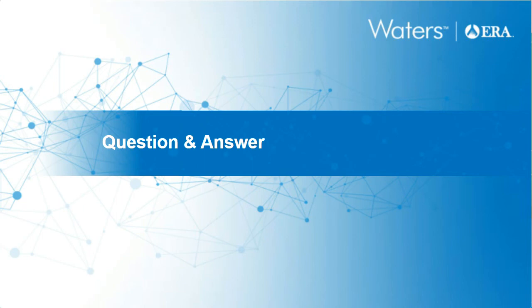I'm trying to think of what is behind that question. The reason I hesitate is the range that matters for whether your result is acceptable or not is literally called the acceptance range, the acceptance criteria, and that is always going to be much tighter than what you're listing there.